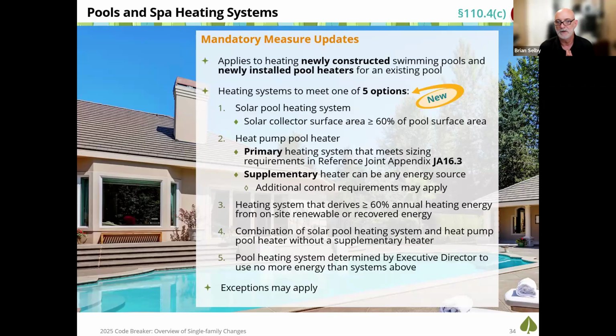So there are 5 options to comply with this. Either install a solar pool heating system with the surface area of the collector at 60% or greater of the pool surface area, or install a heat pump pool heater with the primary heating system sized according to the reference joint appendices chapter 16, specifically JA 16.3.